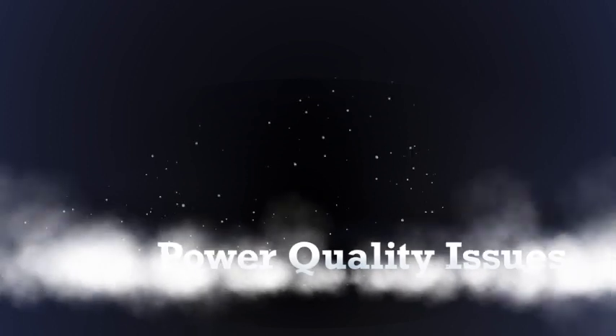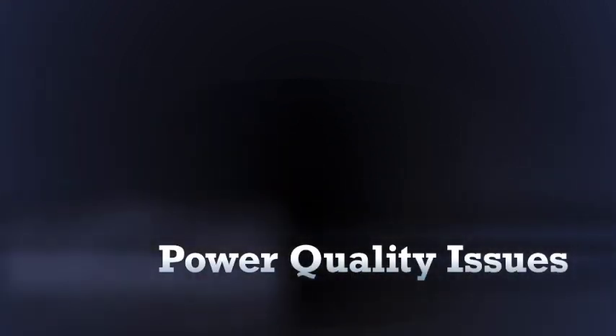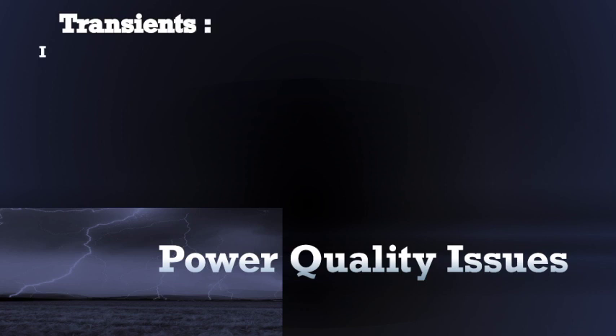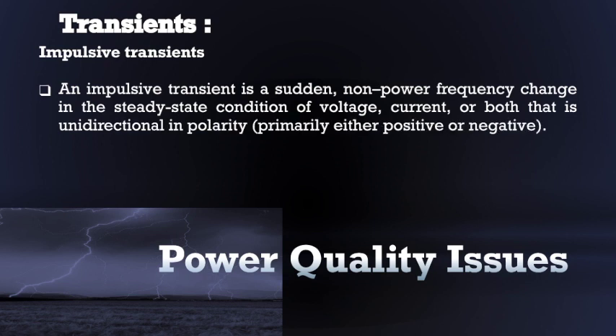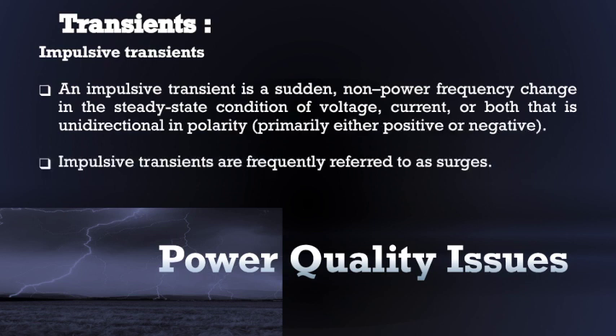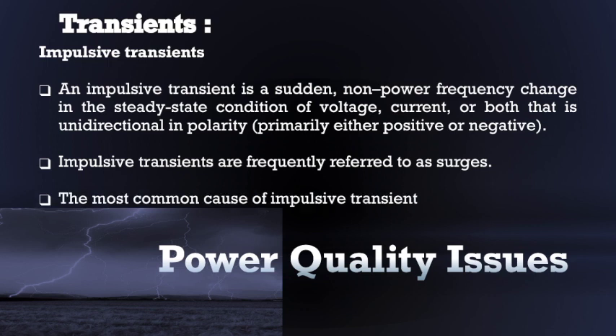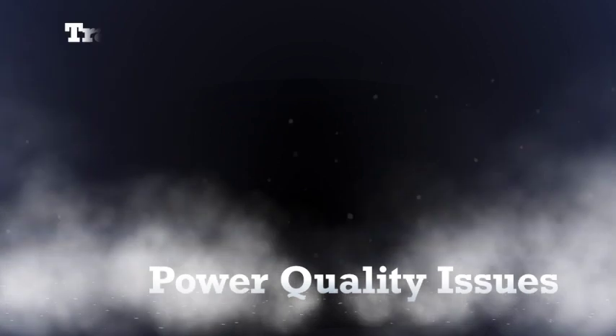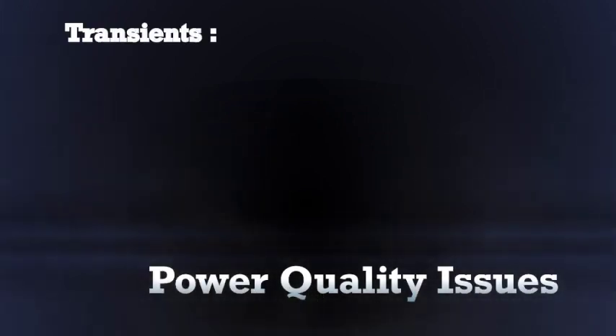An impulsive transient is a sudden non-power frequency change in the steady state condition of voltage, current or both that is unidirectional in polarity. That means the polarity is either positive or negative. Impulsive transients are frequently referred to as surges. The most common cause of impulsive transients is lightning strikes. Other causes include electrostatic discharge, poor grounding, switching of inductive loads, switching of power factor correction capacitors, etc.